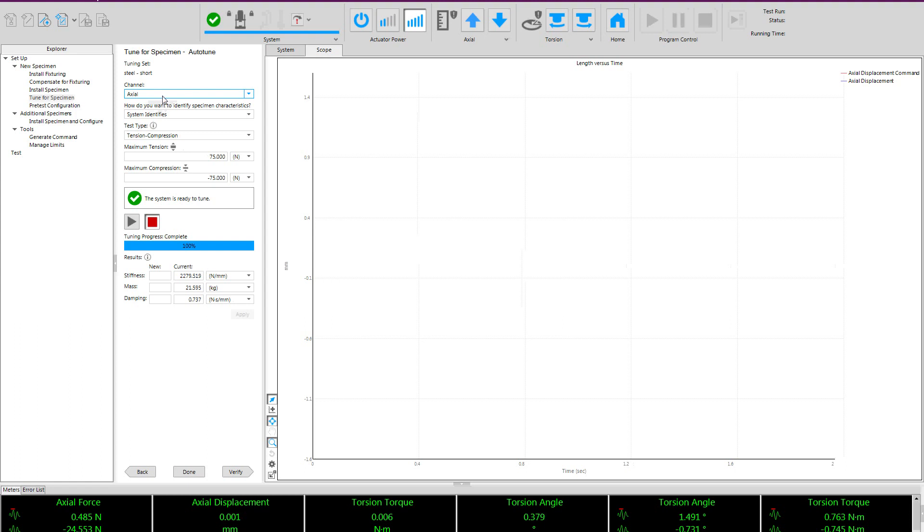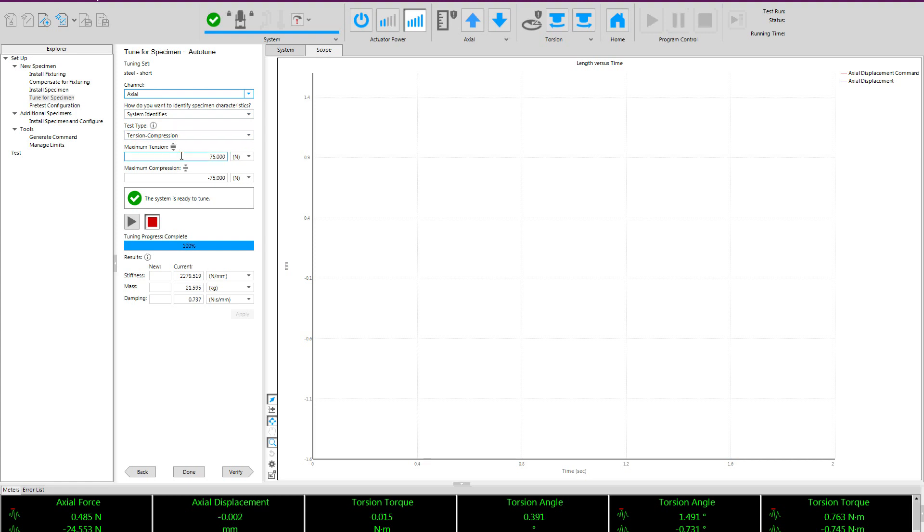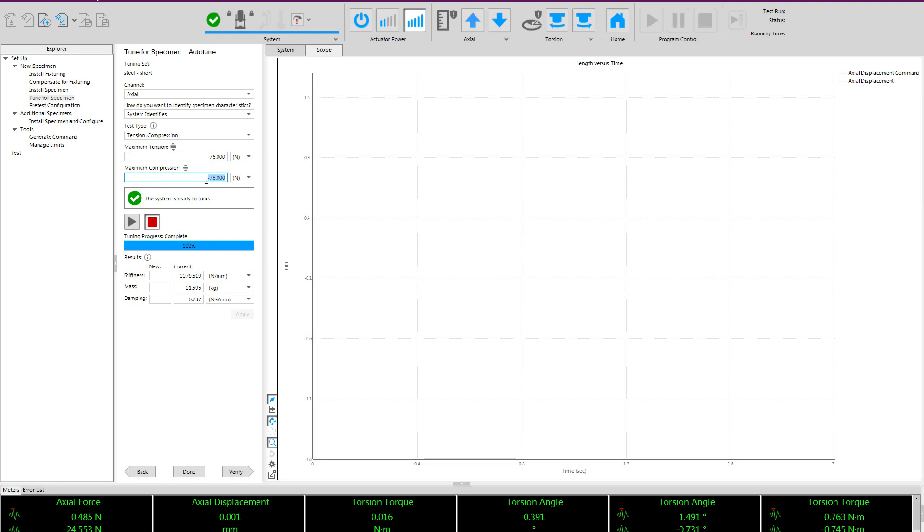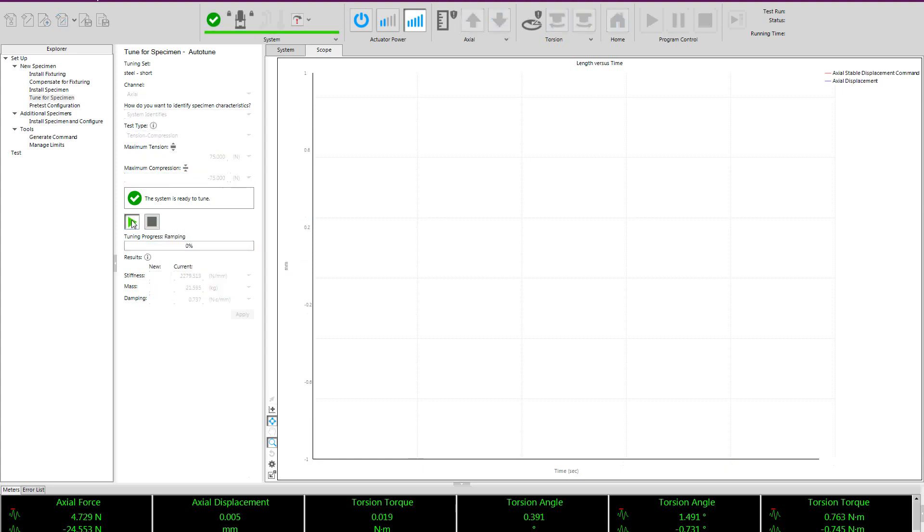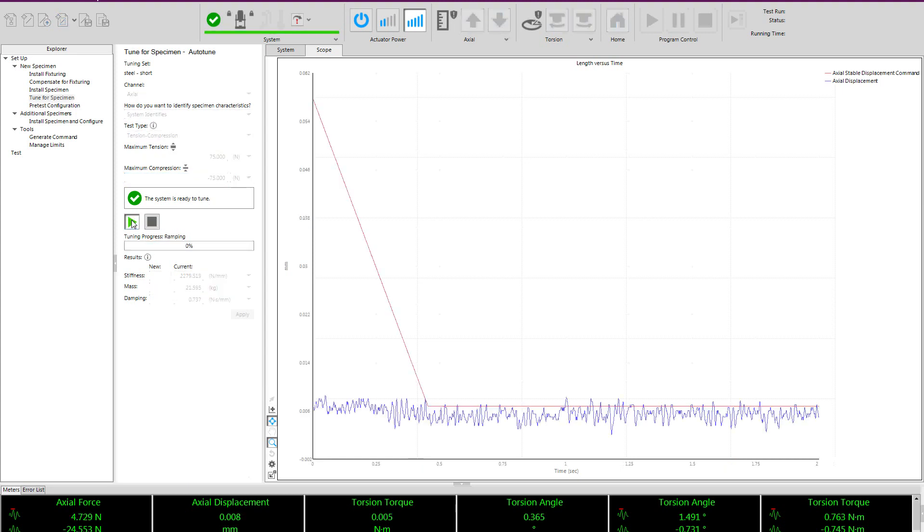So you can see I now selected the axial channel. I select my test type. In this case, it will be tension compression because my sample is rigidly coupled into my test machine. And I enter my minimum and maximum tension and compression values. You can see I enter the values of 75 newtons tension and negative 75 newtons compression. These do not need to be symmetrical, but I chose to make them here. I'll start the procedure to create the axial tuning set.